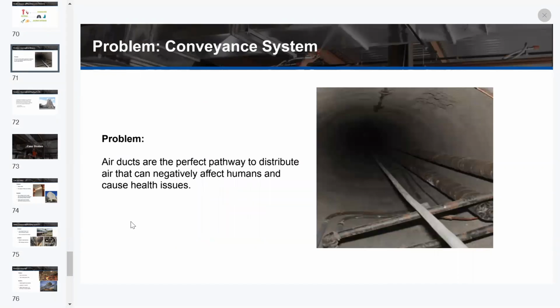So the conveyance system, right? That's the problem. It's not just VOCs that are contributing to the unhealthy air. It's improperly sealed duct. We talked about entraining dirt and debris, which produces unhealthy air that can negatively affect the occupants within a building space. And it's also the perfect pathway or conveyance tool to spread that throughout the whole building.